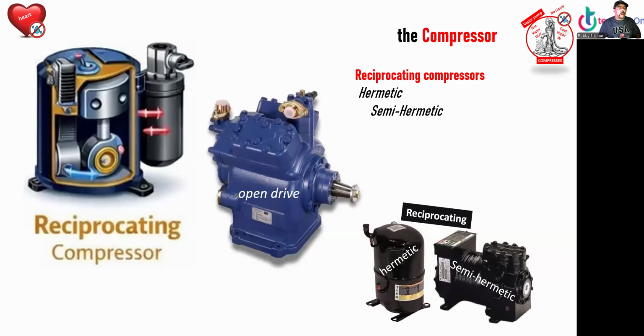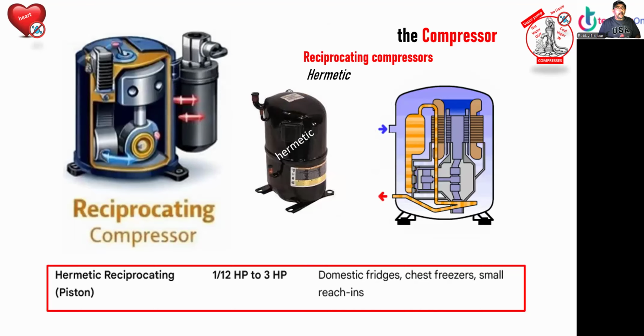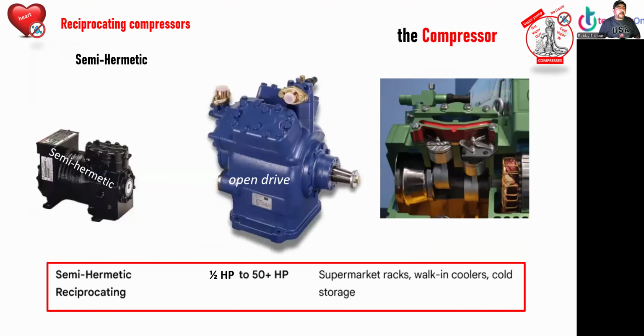Alrighty, let's move on. We have the reciprocating, where pistons go up and down. And we have the hermetic, semi-hermetic, and open drive. The open drive is semi-hermetic. Alrighty. And the reciprocating ones go from 1/12 horsepower to 3 horsepower for domestic refrigerators, chest freezers, small reach-ins, and air conditioning too, I guess. Let me go back. Air conditioning also. Alrighty, let's move on. Now we have the semi-hermetic. Semi-hermetic is from half to 50 horse. You're not going to see this in residential, it's for commercial. And we have the hermetic and open drive.